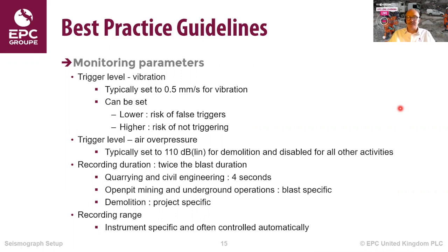Things like that. Now, as for the recording range, we used to be able to set that, but most seismographs these days do auto ranging. But you need to decide, am I expecting a high level or low level, and then set the range accordingly.